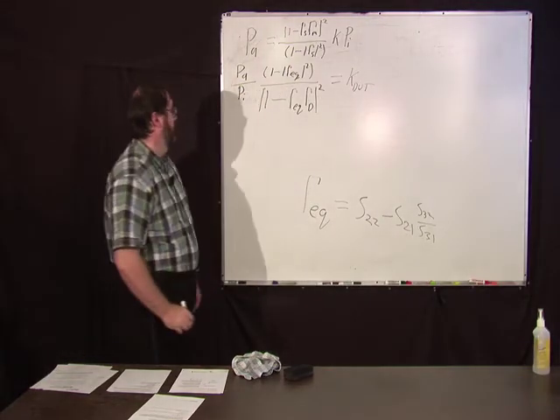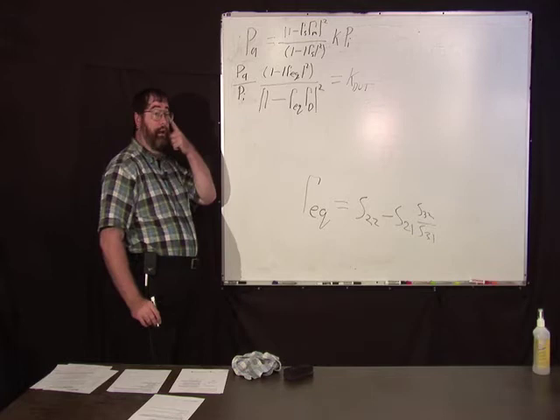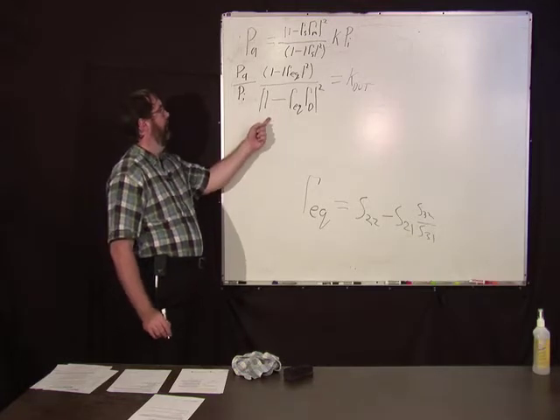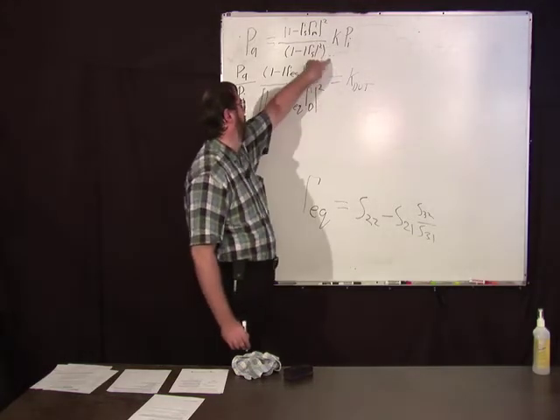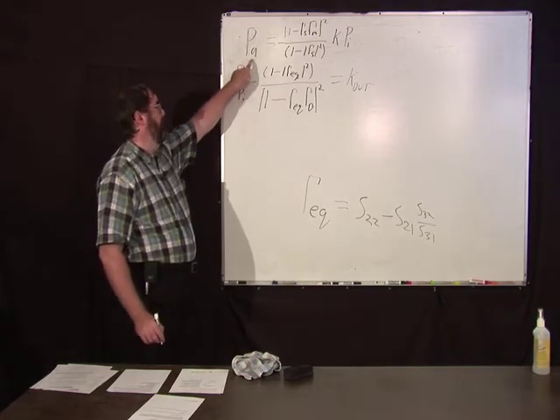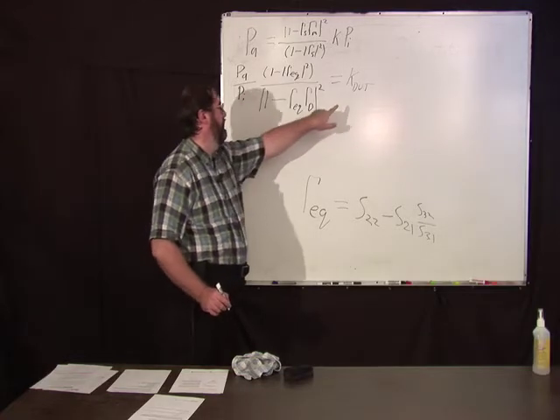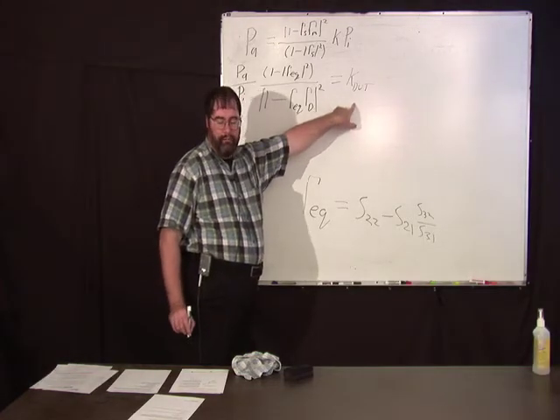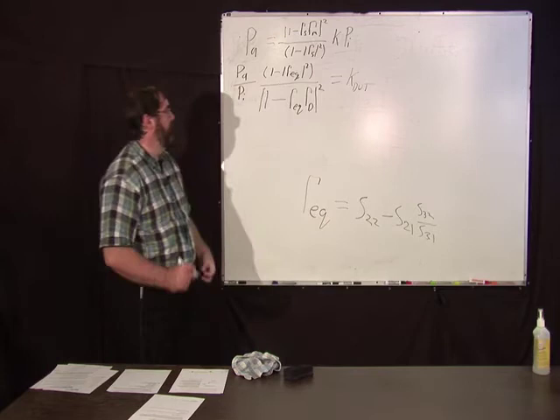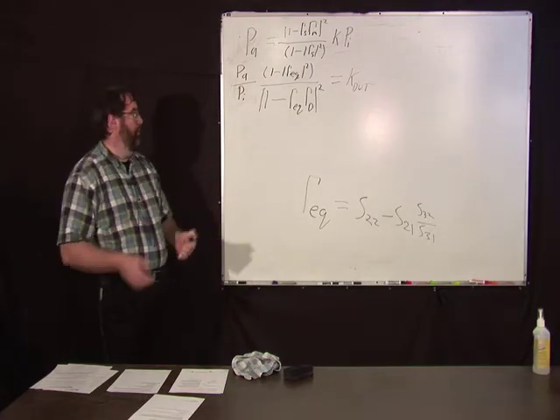So now we've solved the problem. We now have calibrated, we have transferred. This is our standard measurement to give the available power. From that, assuming the same available power and known reflection coefficients, we can figure out the calibration factor of the device under test. That solves the problem if that's all you want to do. But sometimes you have to insert something.